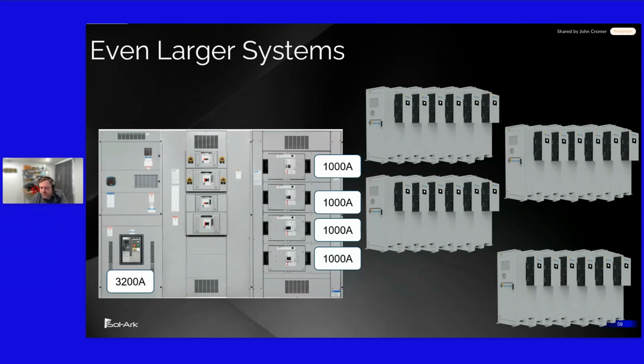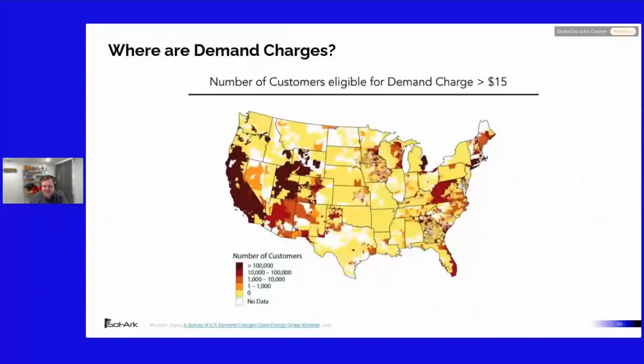You could even do a hybrid where you have a large project where containerized systems make sense, but containerized systems don't provide seamless transfer. So you could have a smaller Sol-Ark system on a commercial industrial site to facilitate seamless transfer of specific devices and applications, and then have a larger 10 megawatt hour plus containerized system providing 1 minute transfer times or longer for the entire facility. A lot of creativity you can do.